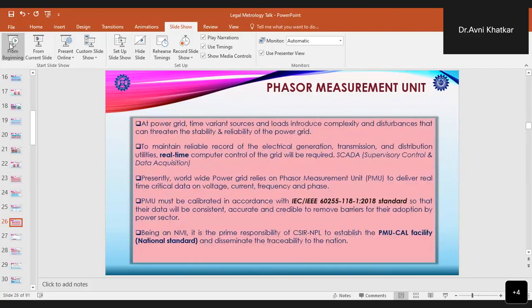And at the power grid, the time variant sources and loads introduce a complexity and disturbances which can threaten the stability and reliability of the power grid. And in order to maintain this reliability of the electrical generation, transmission and distribution, real-time computer control of the grid is required. Initially, SCADA was used. Now, worldwide, the power grid is moving towards the concept of phasor measurement units in order to deliver real-time critical data on voltage, current, frequency, and phase. And these PMUs used in the power grid are so important because they are providing all the information of the grid.